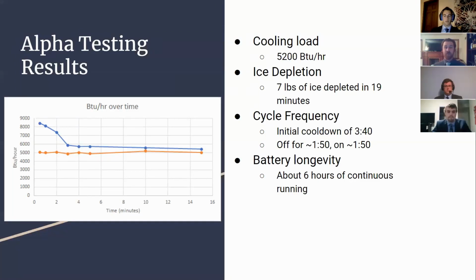For our alpha testing results, we ended up receiving a cooling load of 5,200 BTUs per hour. If you gentlemen want to know how I received this, just let me know and I can go more in depth later on. On ice depletion, it's important to understand our system was running nonstop, and we burned 7 pounds of ice in 19 minutes. This is 19 minutes straight of runtime, and in a normal setting, it will cycle on and off. Our cycle frequency without the insulation: the initial cool down was 3 minutes and 40 seconds. It was off for 1:50 and on for 1:50, and it continued to do this.